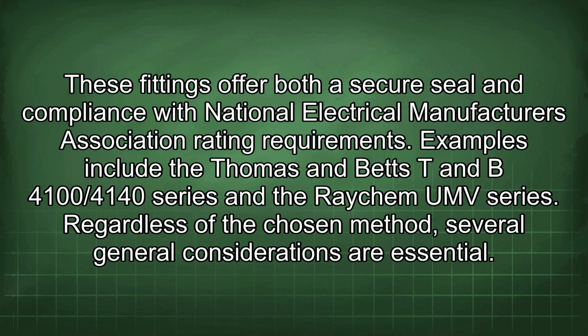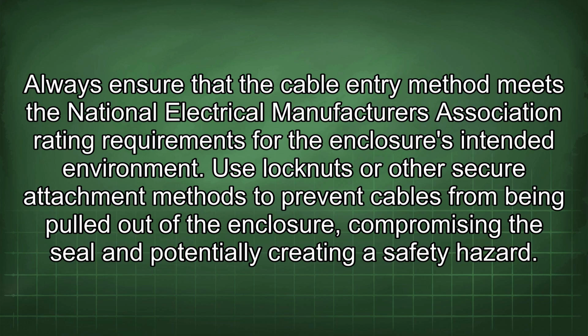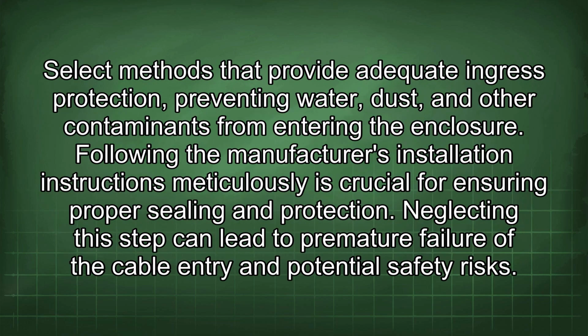Regardless of the chosen method, several general considerations are essential. Always ensure that the cable entry method meets the National Electrical Manufacturers Association rating requirements for the enclosure's intended environment. Use lock nuts or other secure attachment methods to prevent cables from being pulled out of the enclosure, compromising the seal and potentially creating a safety hazard. Select methods that provide adequate ingress protection, preventing water, dust, and other contaminants from entering the enclosure. Following the manufacturer's installation instructions meticulously is crucial for ensuring proper sealing and protection. Neglecting this step can lead to premature failure of the cable entry and potential safety risks.